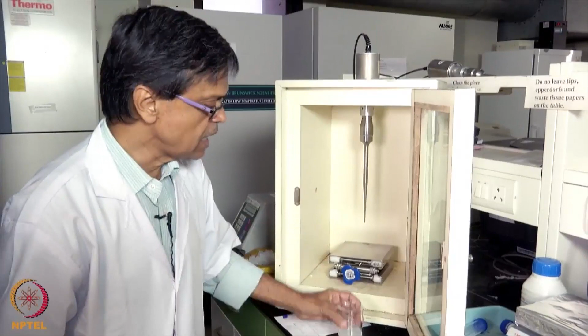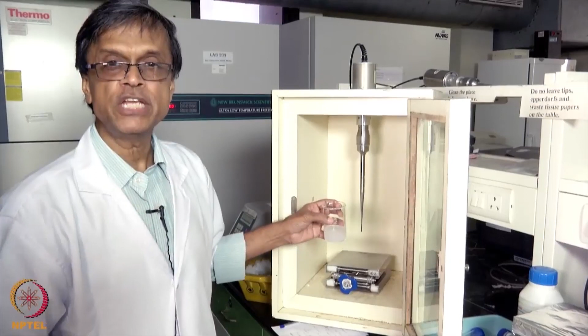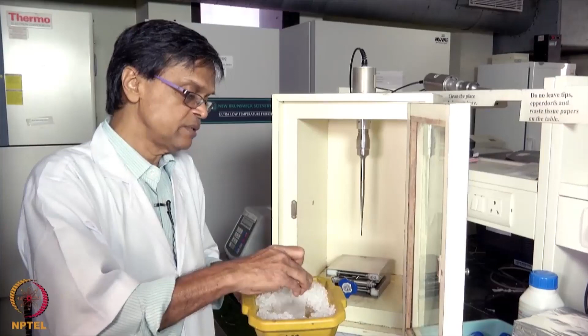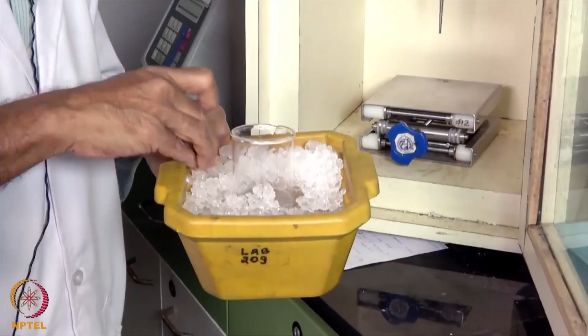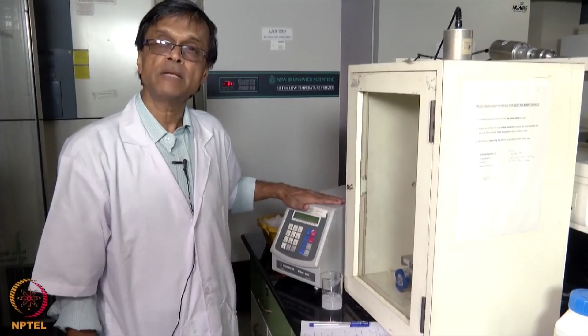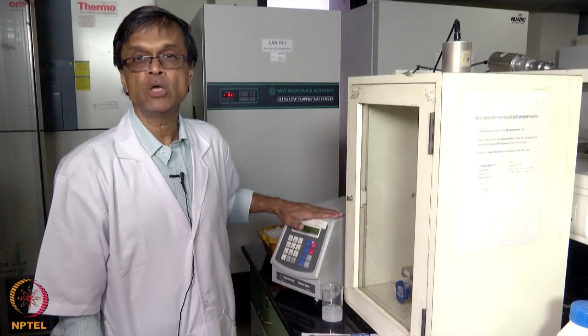This is the probe sonicator, and we have to keep our sample inside. The sonication will be done for 5 minutes. The sonication will be on for 9 seconds and 1 second off. Because a lot of heat is produced, we have to keep the whole sample inside the ice bath. As you can see here, this is the control unit for the probe sonicator. So we need to set this control. We are going to sonicate for 5 minutes. It will not be continuous, there will be pulses and then stop, but every 9 seconds there will be a pulse and 1 second off.